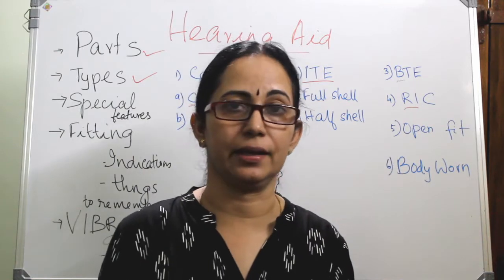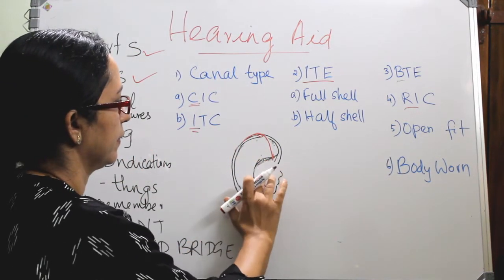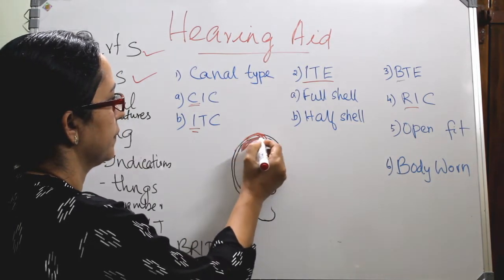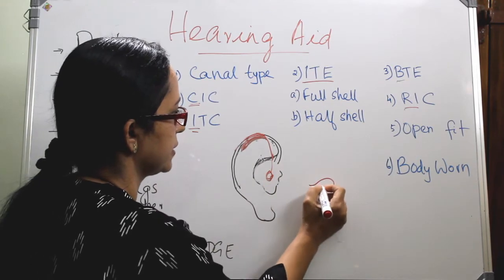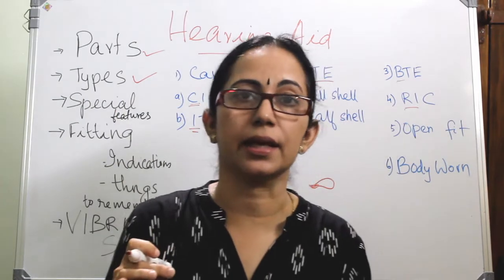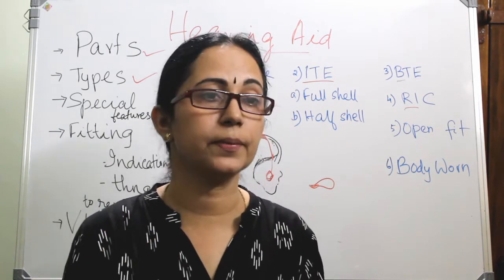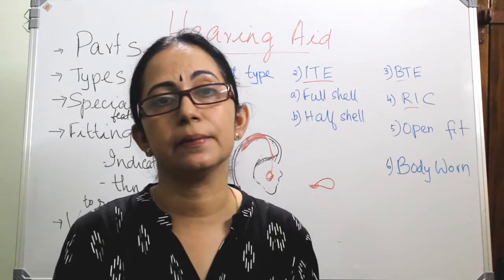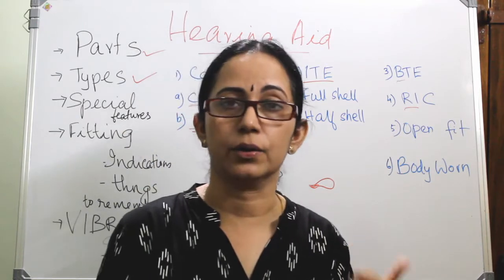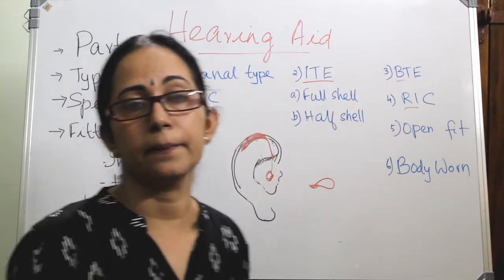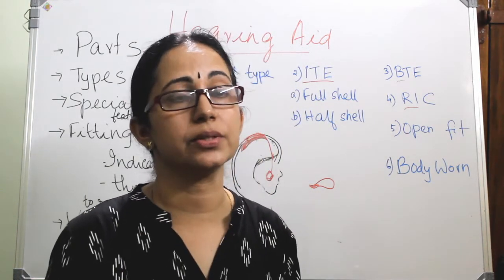RIC (receiver in the canal), also called mini BTE, is a smaller version of BTE. The main unit sits in the upper part of the ear connected to a very small ear insert kept inside the ear canal, making it less visible. Advantages include volume control, directional microphone, and easy manipulation. Disadvantages include wind noise pickup and risk of the receiver being clogged with wax. RIC is especially preferable for high frequency sensorineural loss, particularly in presbycusis.